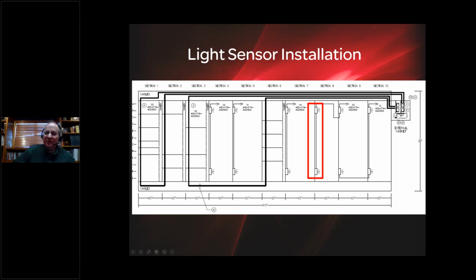And what we did is we mounted a small external cabinet. You can see that on the right side of the drawing there, and I'll highlight it for you, where we put the annunciation panel and the sensor relays, since there was no physical room inside the MCC. I would say 7 times out of 10 with an existing MCC, we're able to find room for that. We also have a DIN rail mounted version of the sensor relays, which can be installed in the top or bottom wire troughs of the motor control center itself.